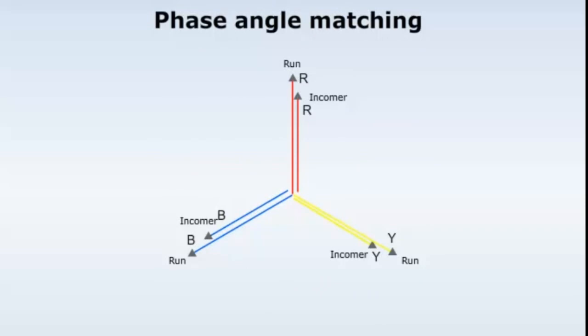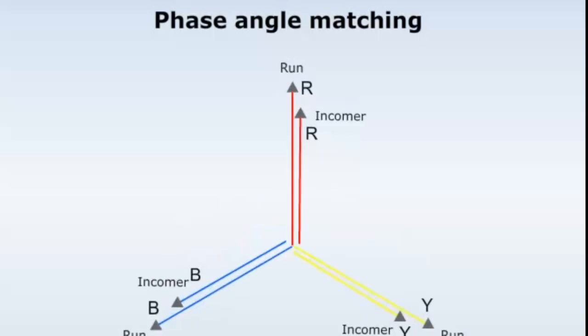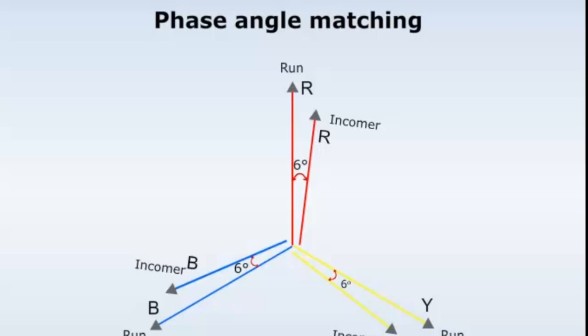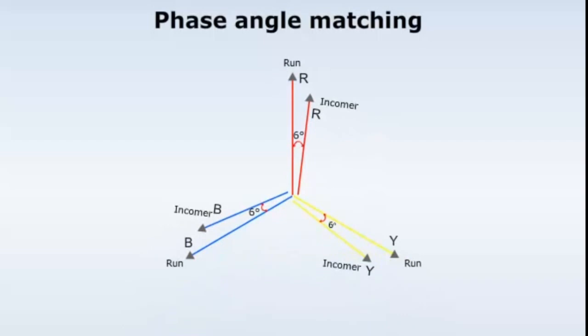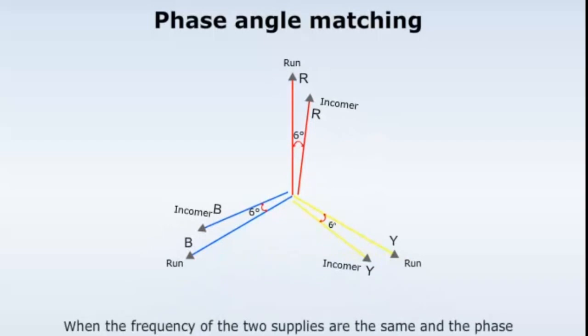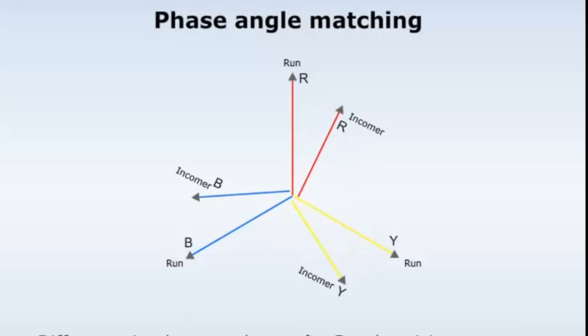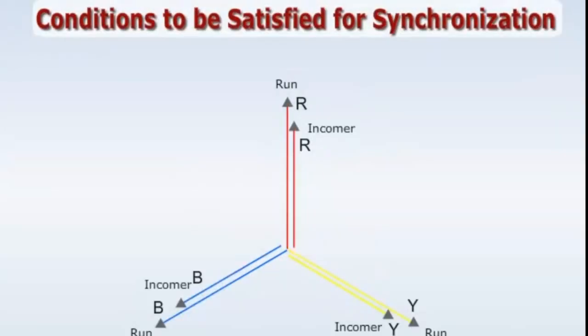The fourth condition is that the phase angle of the incoming alternator should match the phase angle of the running alternator. The phase angle between the two alternators should be within six degrees. This condition can be obtained only when the frequencies of the two supplies are the same and the phase sequences are also the same. A difference in phase angle between the running and incoming alternator at the moment of paralleling will produce synchronizing currents.